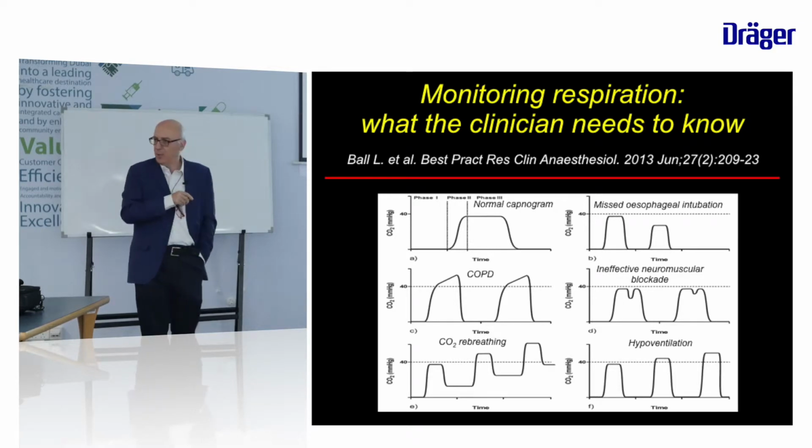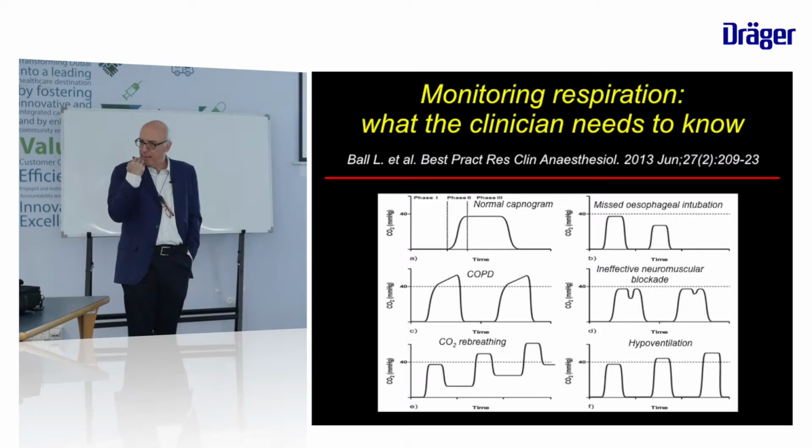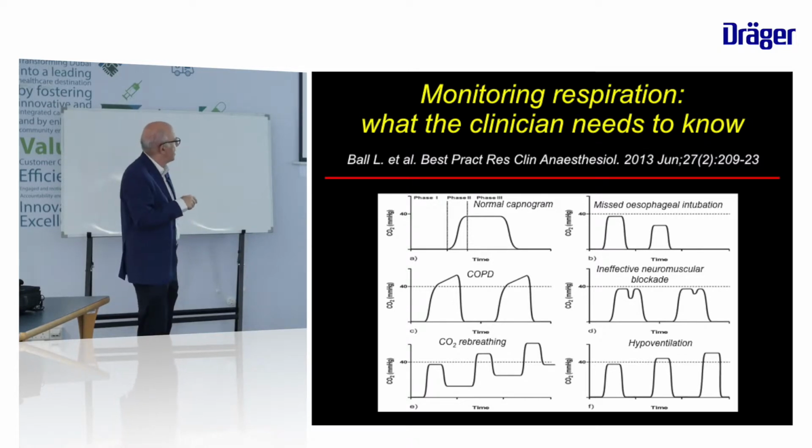underestimate the end-tidal CO2. Okay? Because you need time in order to reach the equilibrium between the alveolar CO2 and the CO2 in the blood. When you have CO2 rebreathing, you have a progressive increase in the end-tidal CO2, but also at inspiration. You see here at inspiration.